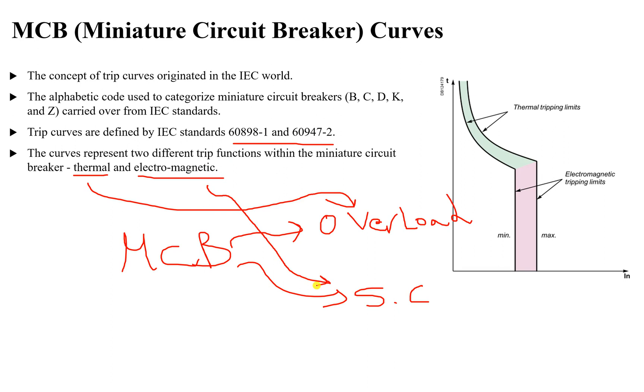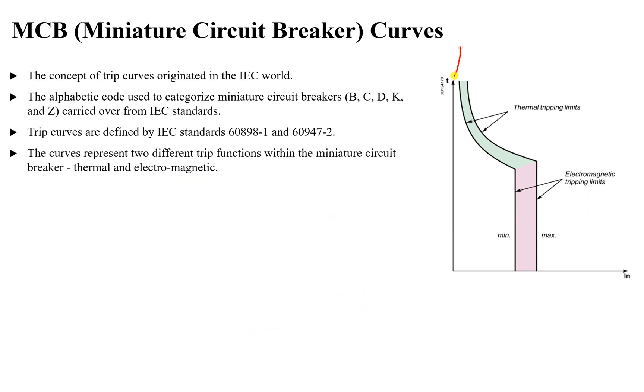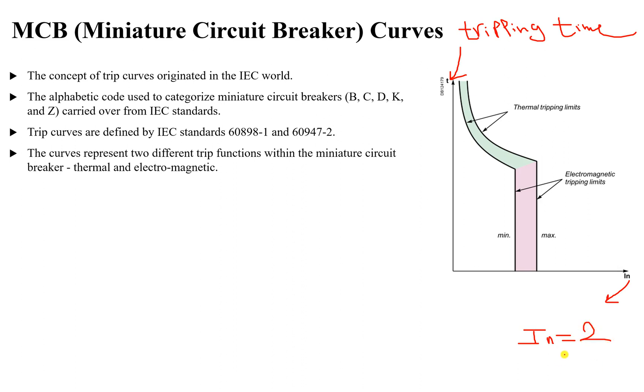If you look at any trip curve, the Y-axis represents the tripping time — the time required for the circuit breaker to trip the electric circuit. On the X-axis we have In, which is a multiplier of the current. In means how much our current is with respect to the rated current. For example, if In equals 2, our current is 2 times the rated current; if In equals 3, it is 3 times the rated current.